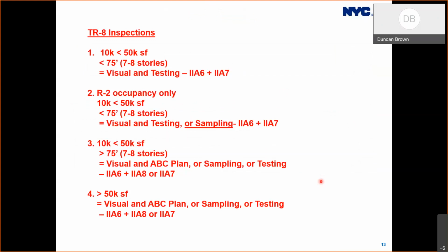So for commercial buildings under 10,000 square feet, they just require a visual inspection. And for buildings greater than 10,000 square feet and less than 50,000 square feet that are also less than 75 feet high, that's to say 7 to 8 stories high, they require visual inspection and testing. And if they're a building of that size and they're R2 occupancy only, then they also have the option of sampling or unit testing.